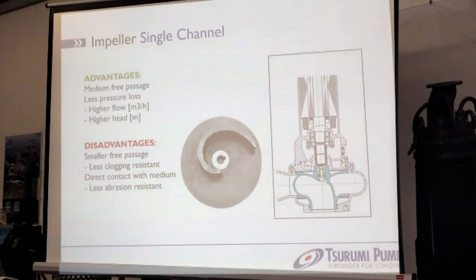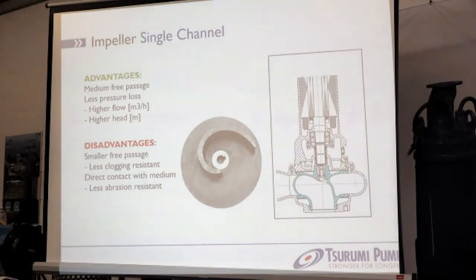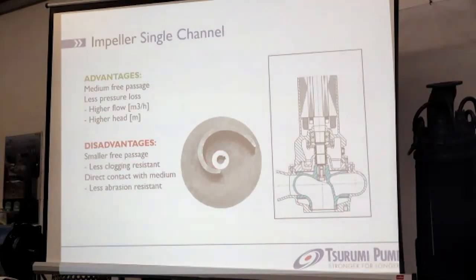Disadvantages are the smaller free passage compared to the vortex pump, making it automatically less clogging resistant. There is direct contact with the medium at the impeller vanes because this impeller directly pushes the medium away — we are talking about a direct pumping effect, not indirect. Due to this direct contact with the medium, we are also talking about a less abrasion-resistant impeller form.